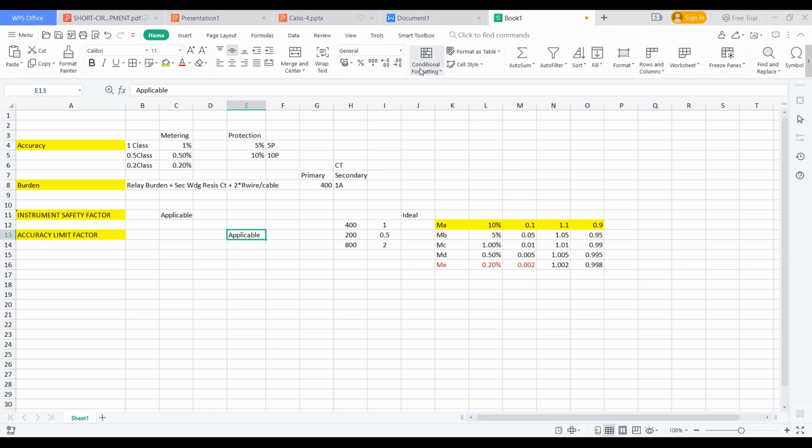Generally, if you check the current transformer magnetizing characteristics, I mean the BH curve, a current transformer with a given core dimension can only support a given amount of flux density in the core. As long as the flux density remains below the maximum flux density, a change in flux will create a current flow in the secondary side. Once the primary current is high, reaching more than a certain limit, the core of the CT cannot handle any more flux, and the CT is said to be in saturation.